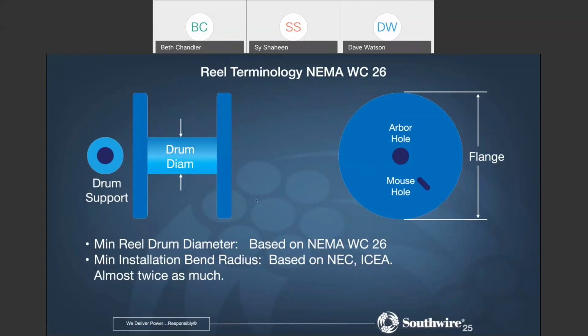A lot of times I get, hey, Sy, you sent me a cable where the drum diameter is X. Meanwhile, you violated the bending radius of this cable because you put it on a bend radius that is less than what the NEC or ICEA asked for, which is almost twice as much. Well, again, the reason is because when you're on a reel, we go by NEMA WC26, and you're not under tension, you're not pulling it, and so forth. So the minimum bending radius on a reel is always going to be smaller than what we ask you for in the field, which is normally the OD.